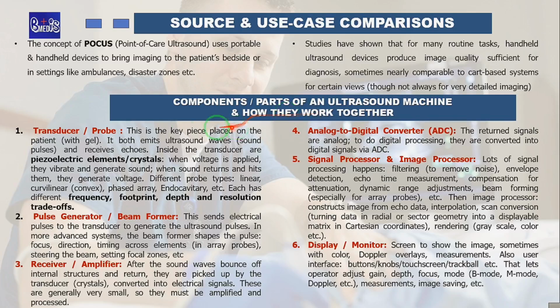First and foremost, we have the transducer. The transducer is the probe. This is the key piece placed on the patient with gel. It both emits ultrasound pulses and receives echoes. Inside the transducer are piezoelectric elements, or crystals. When voltage is applied, they vibrate and generate sound. When sound returns and hits them, they generate voltage.